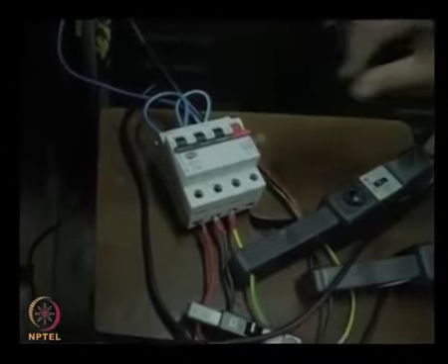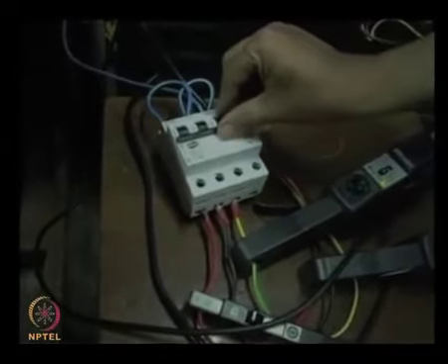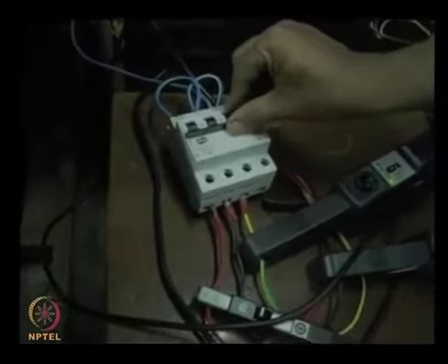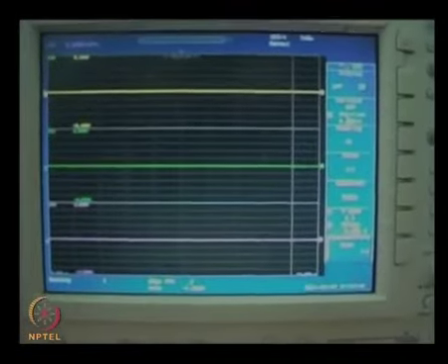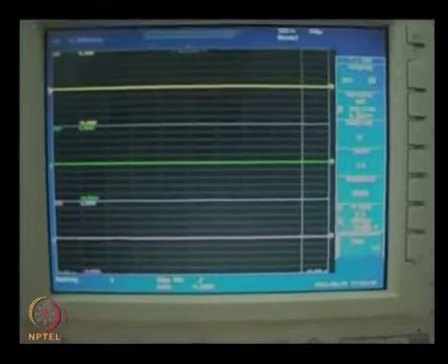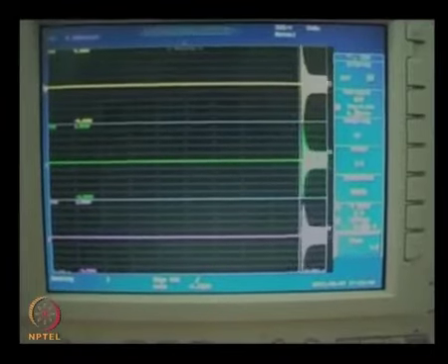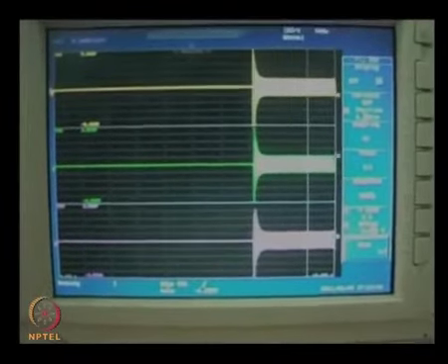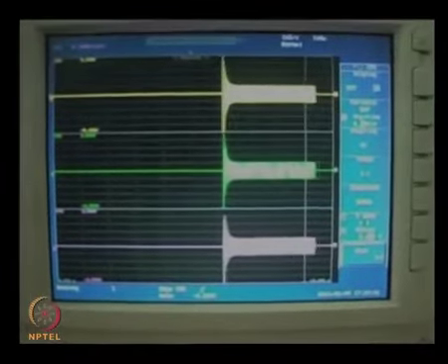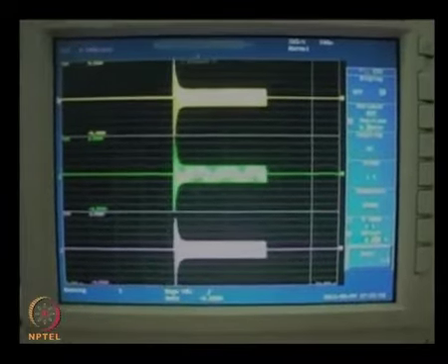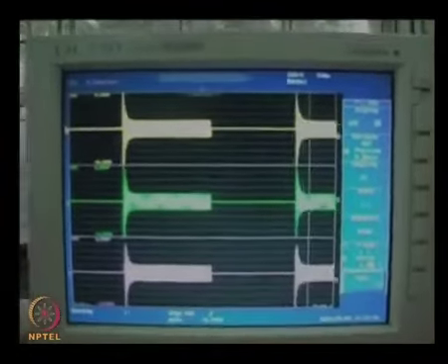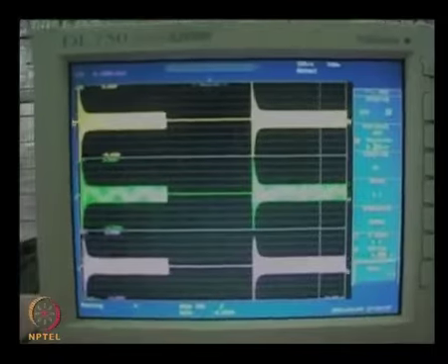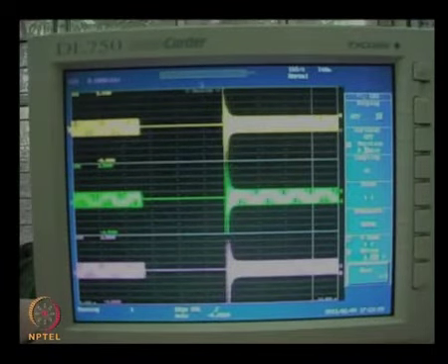Now we will actually perform the short circuit by connecting all the three phases together. The MCB will have to be switched on to the on position and we will simultaneously view the short circuit. It will be any time now. He has given the short circuit and you see that large envelope in the beginning which decays. You will also see a DC offset, it is not very clear here. I will show you the actual figures.